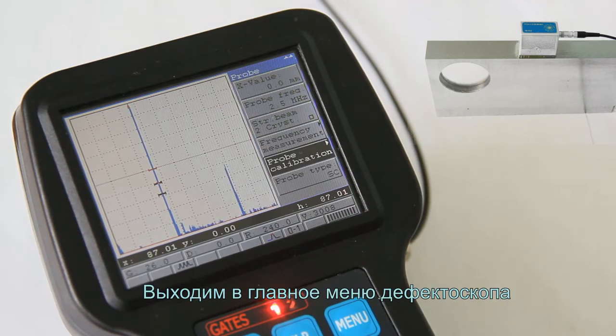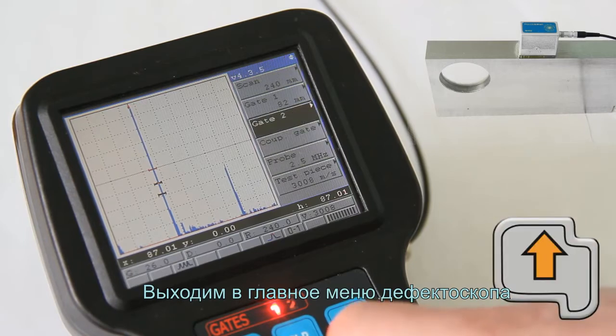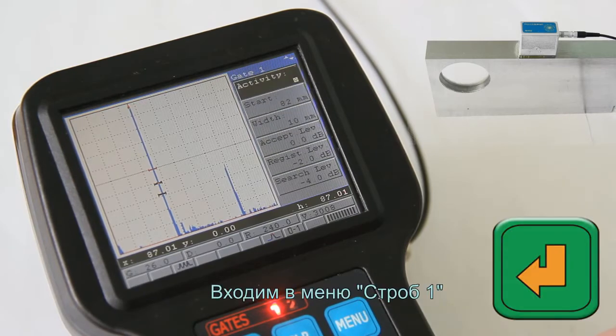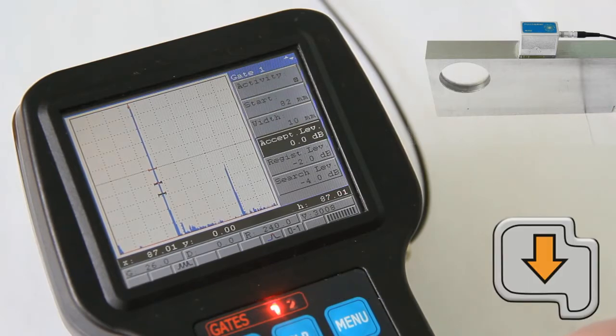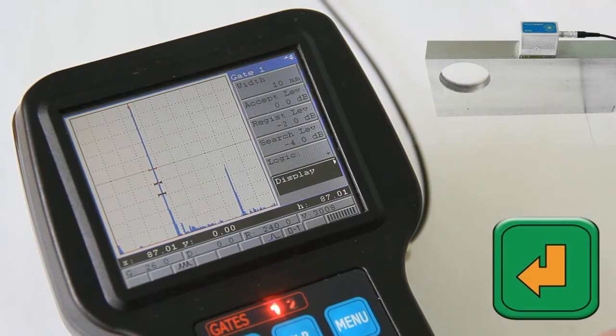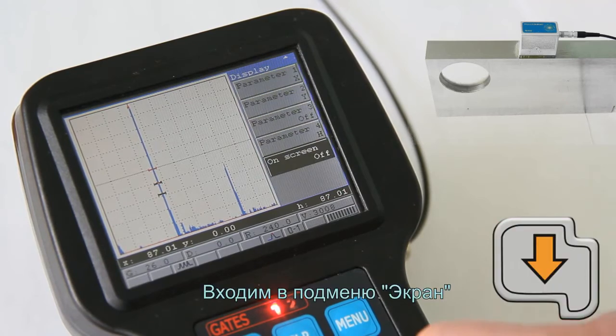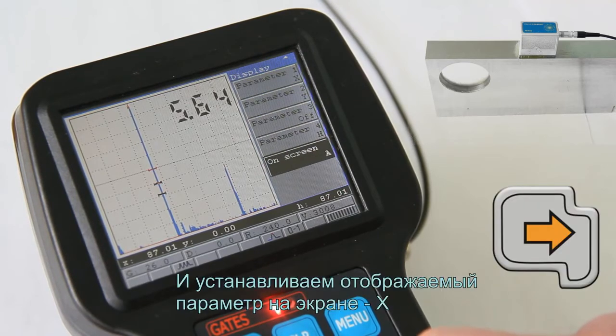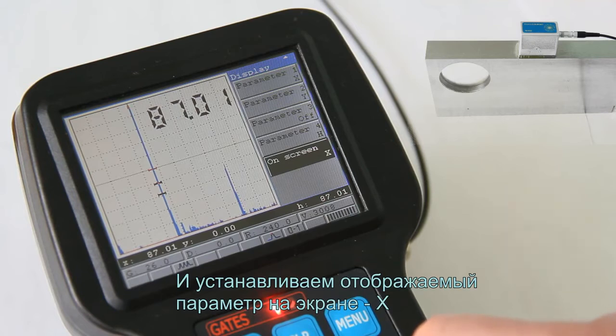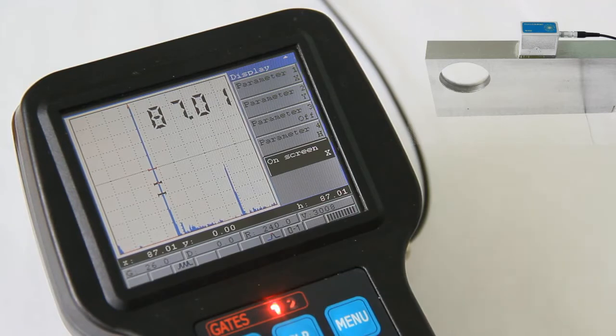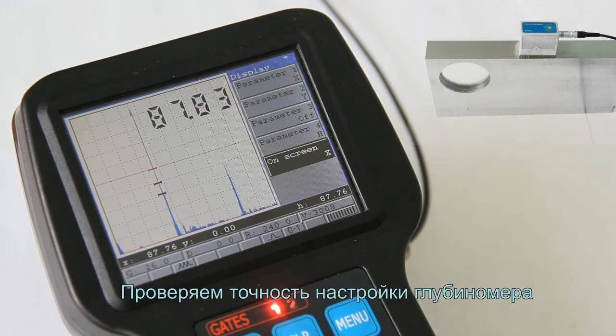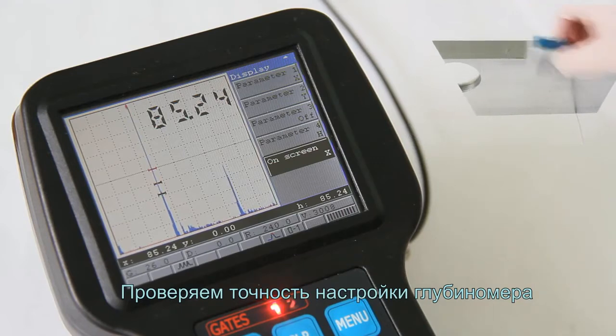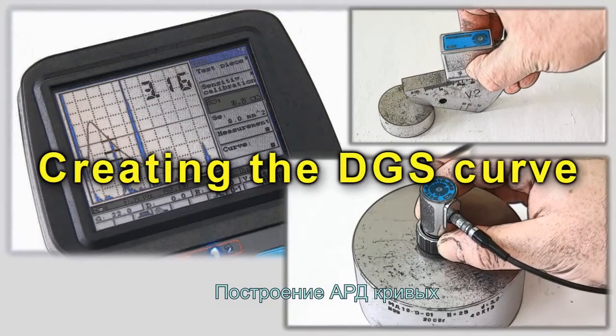Return to the main menu of the Flaw detector. Enter the Gate 1 menu. Enter the Display submenu and set up the X coordinate displayed on the screen. Check the accuracy of the depth gauge setup. Creating the DGS curves.